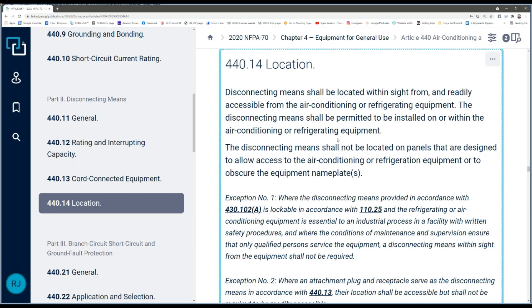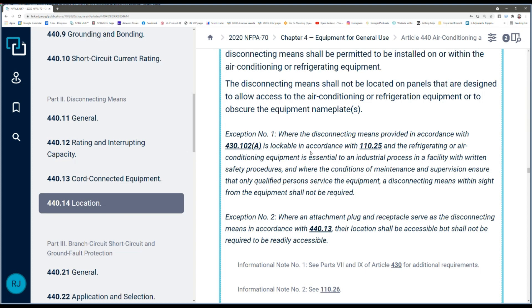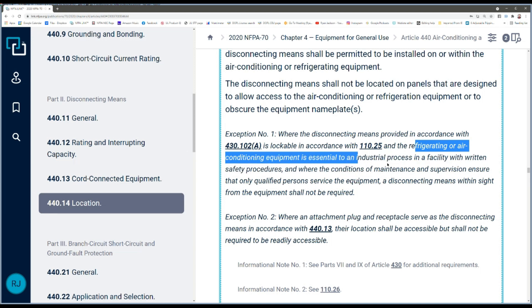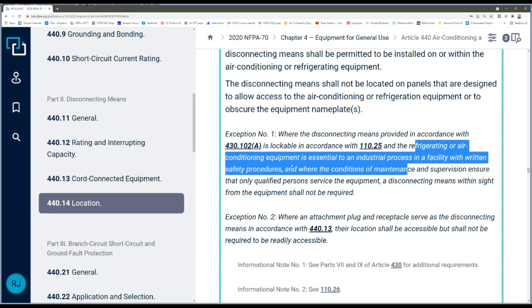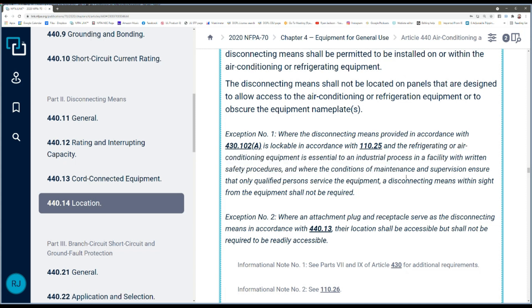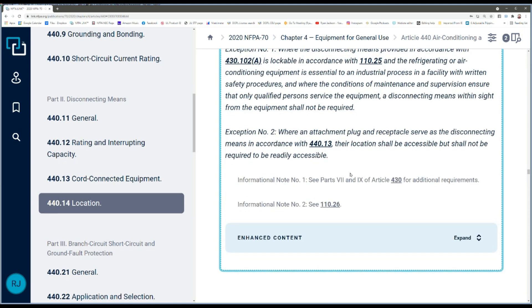You need to have a disconnect, and it has to be within sight — that'll be the topic of the next video. For the outdoor unit, a disconnecting means within sight is required. Some motors have exceptions allowing a disconnect not within sight if it's lockable in the open position, but for air conditioning equipment that exception only applies where the equipment is essential to an industrial process in a facility with written safety procedures. A house doesn't satisfy those requirements, so you must have a disconnect at the outside unit.